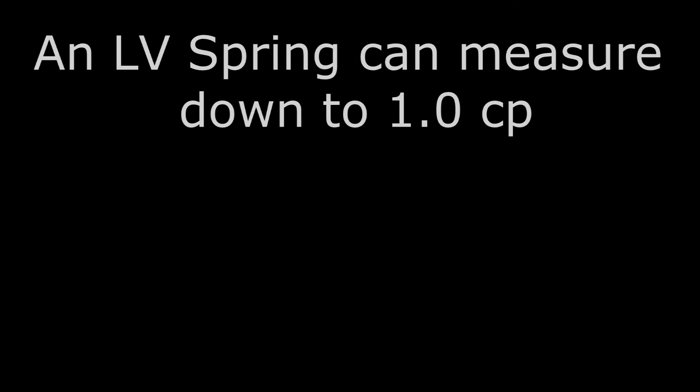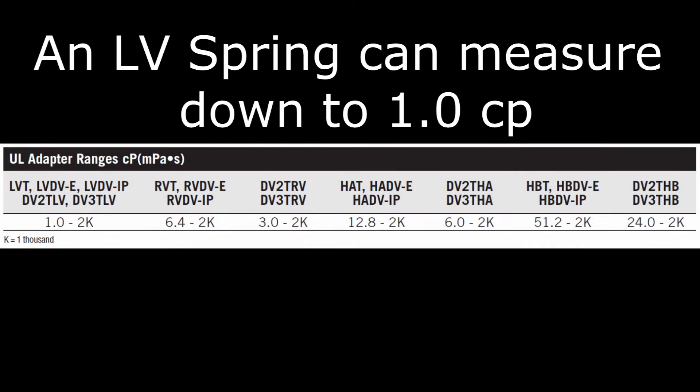When used with an LV spring, you can measure as low as one centipoise. Here are the measuring ranges for the different springs we offer.